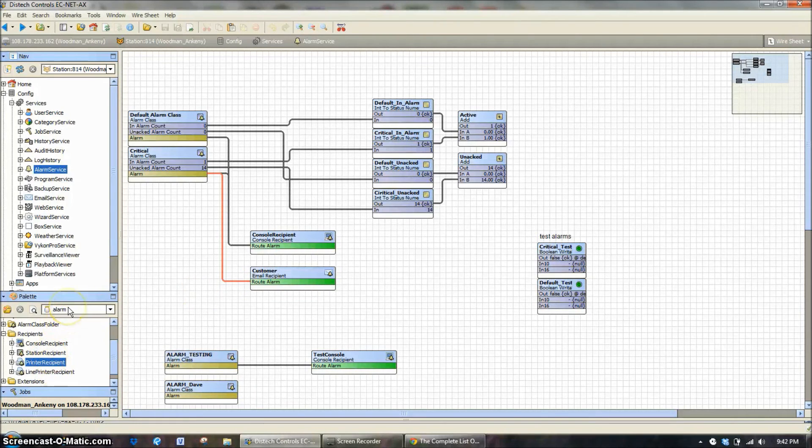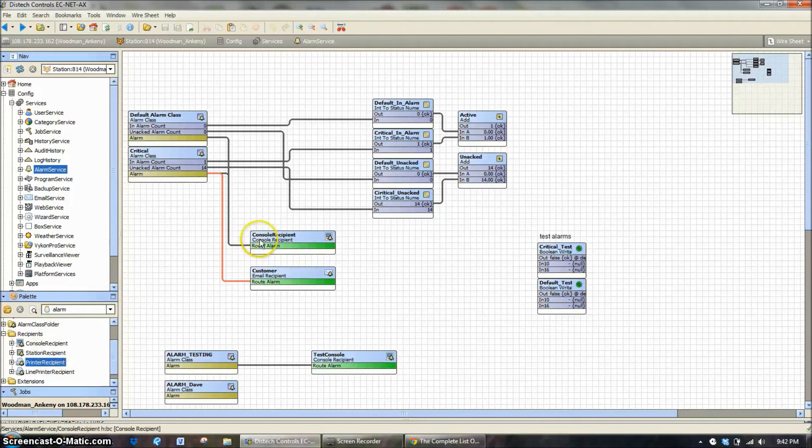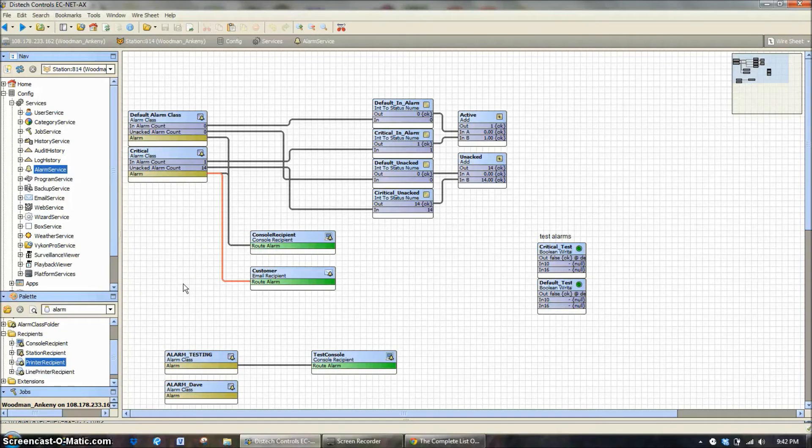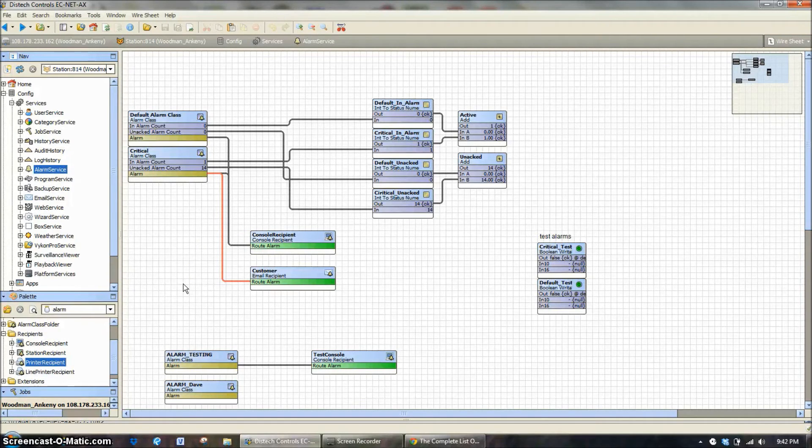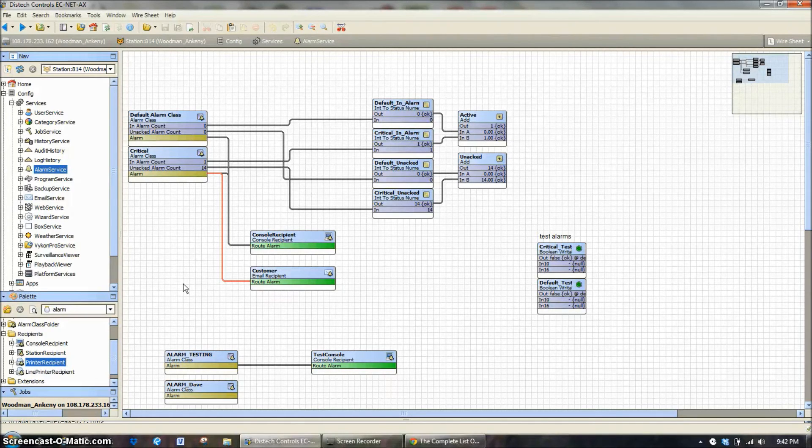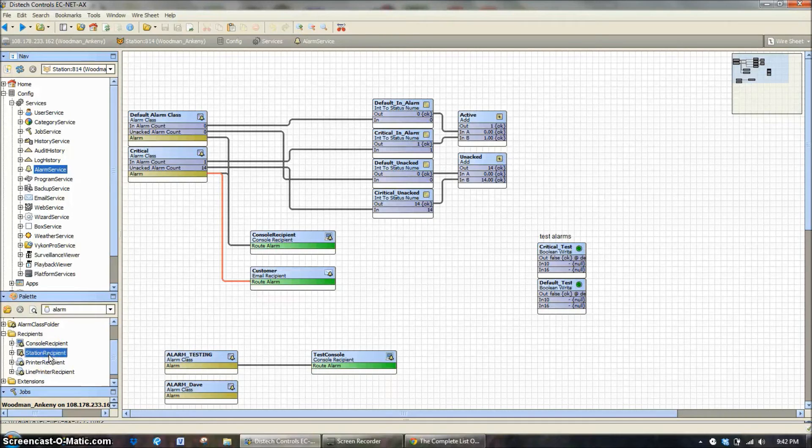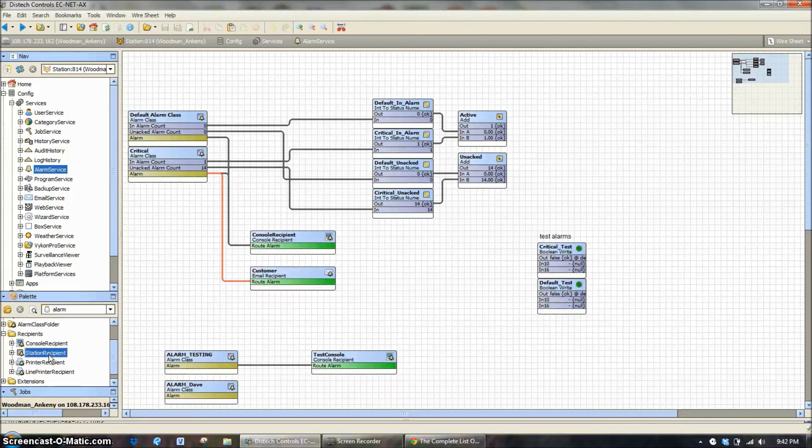Now over here in the alarm pallet, there's a console recipient, which is what we already have. Now, we talked about this in a previous training class. There can be multiple console recipients. So you could have one set up for a security station, one set up for a maintenance crew, one set up for an HVAC contractor. There could be multiple consoles that people might want to look at. The station recipient is used if you have multiple sites and you only want to log into one building and see alarms from multiple buildings.